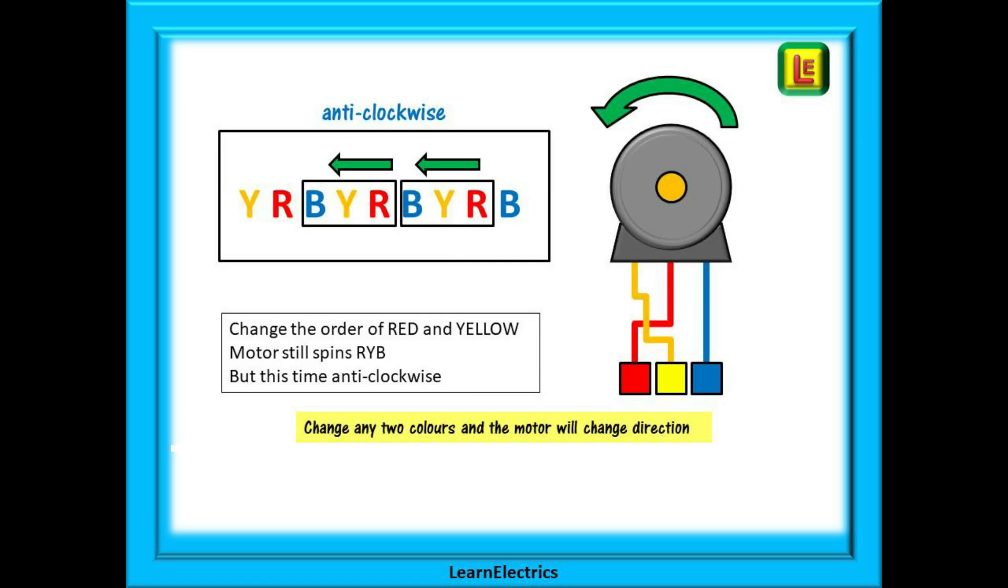If we swap any two phases, in this case the red and yellow, our order is now yellow, red, blue. But if we look closely at the diagram, what have we got? The sequence of red, yellow, blue is still there, but now it is from right to left, the opposite direction. The motor will still follow red, yellow, blue, red, yellow, blue, but now it rotates in the opposite direction. It rotates anti-clockwise. Swap any other two colors and it will change direction again. A very simple concept, remember it, it will make you look good on site.